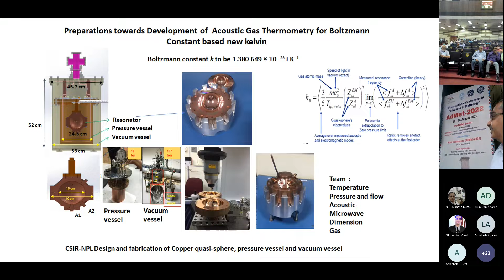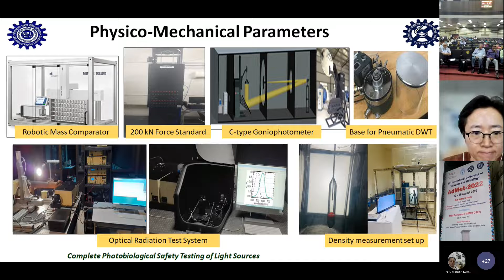In other physicochemical parameters, what we have set up in the last 1 year includes a robotic mass comparator, which has been installed, and a 200 kilonewton force standard. There's a C-type goniophotometer, which is also linked to the optical radiation test system. This can measure up to 2-meter light sources, so you can calibrate and test them. This is a base for the pneumatic DWT. This is the density measurement setup, which is also operational now.